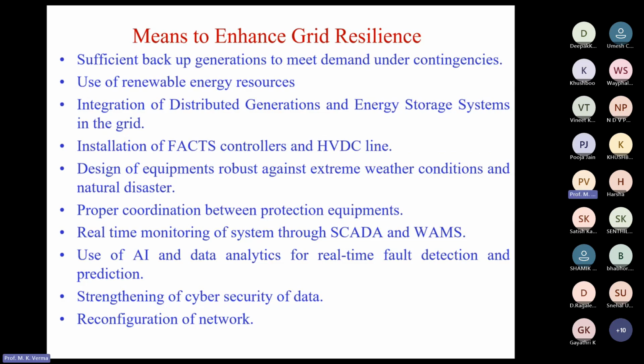Now, how can you enhance the resiliency of the grid? There must be sufficient backup generation to meet demand under contingency. Suppose some outage occurs, and we are unable to supply from the routine generators which are supplying this area. You should have some backup generation, maybe in the form of decentralized and distributed generation that can locally supply that part of the network so that the system can recover. So there should be sufficient backup generation.